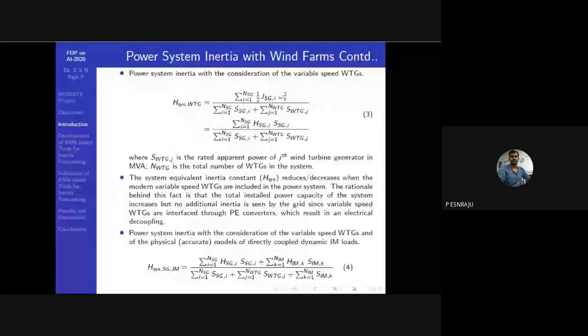So now we will see how the power system inertia is going to change with the consideration of variable speed wind turbine generators. If you see the previous equation, when we integrate variable speed wind turbine generators through the power electronic interface, these will not be directly coupled to the grid. So these will not contribute any inertia to the power system. In the numerator, we have the energy stored in the synchronous generator that is directly coupled to the grid and supplies to the grid.